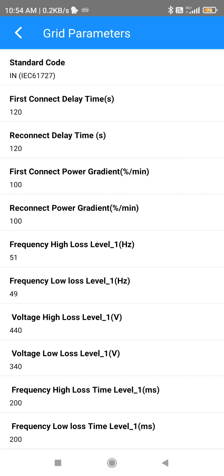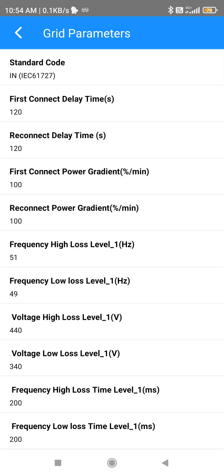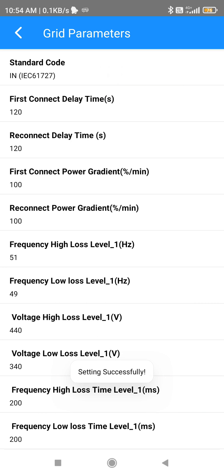After entering the grid parameters, the first thing you have to observe is the Standard Code. If some other code is there, make sure you select IEC 61727. After selecting that, refresh it — the other parameters below will also get changed and will reflect accordingly.